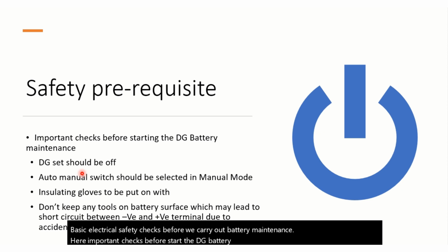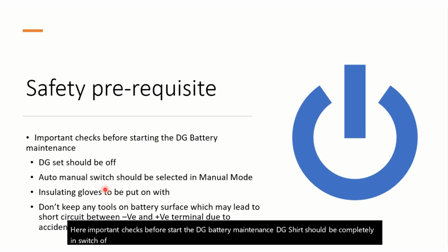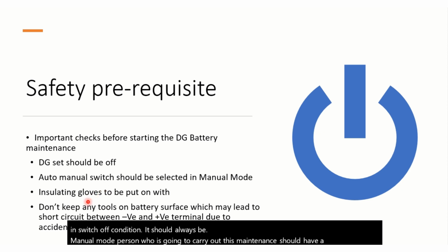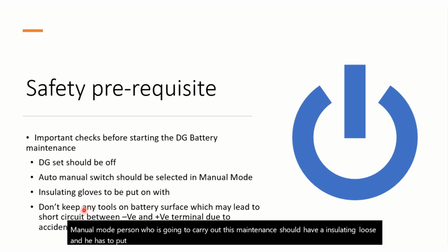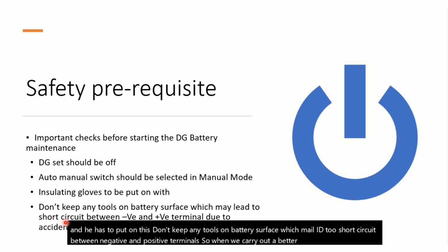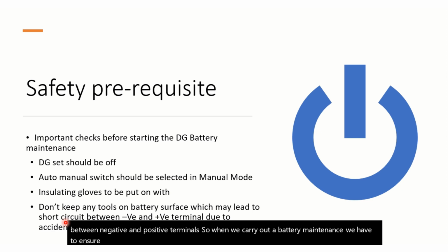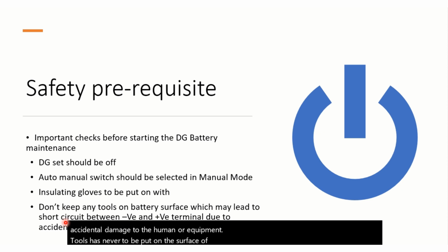The DG set should be completely in switched-off condition. It should always be in manual mode. The person who is going to carry out this maintenance should have insulating gloves and put them on. Don't keep any tools on the battery surface, which may lead to a short circuit between the negative and positive terminals. So when we carry out battery maintenance, we have to ensure that our tools are insulated and our hand gloves are on, and to prevent any accidental damage to the human or equipment, tools should never be put on the surface of the battery while doing any maintenance.